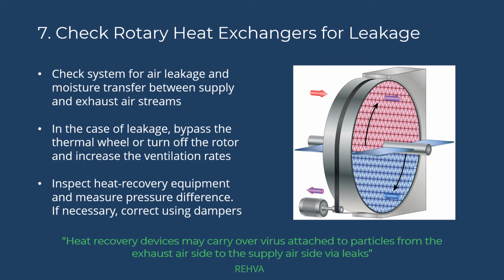Newer and/or larger HVAC systems may have heat exchangers. According to REHVA, these may carry over virus-laden particles from the exhaust air side to the supply air side via leaks. Under certain conditions, these virus particles in extract air could re-enter the building. Poorly designed or maintained rotors may be prone to leakage. However, REHVA says that virus particle transmission via heat recovery devices is not an issue when an HVAC system is equipped with a twin coil unit or another heat recovery device that guarantees 100% air separation between return and supply side.